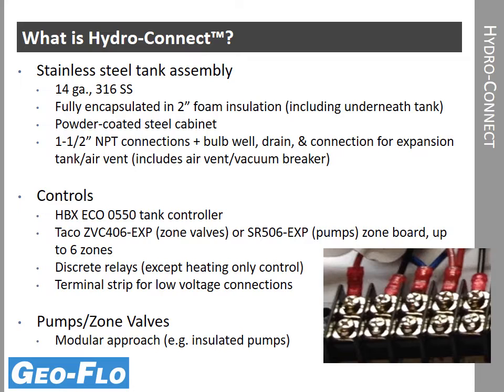The tank is stainless steel. It's 14 gauge 316 stainless, and it's fully encapsulated in a powder coated steel cabinet. That allows us to have 2 inches of foam insulation, including under the tank. We have a design that allows that tank to sit up off from the bottom and allows foam to be underneath the tank itself. So that will certainly help with any kind of chilled water application. It's not as necessary for hot water, although it does help with tank losses. But on chilled water, we're concerned about condensation, and that 2-inch foam insulation is very helpful for condensation.